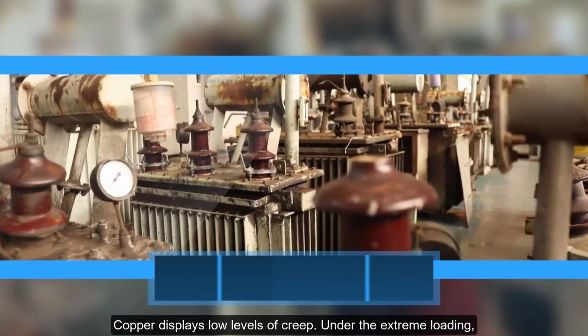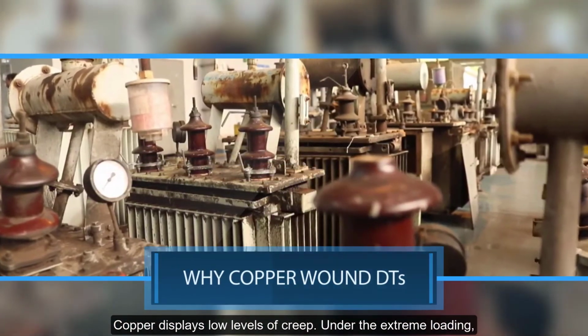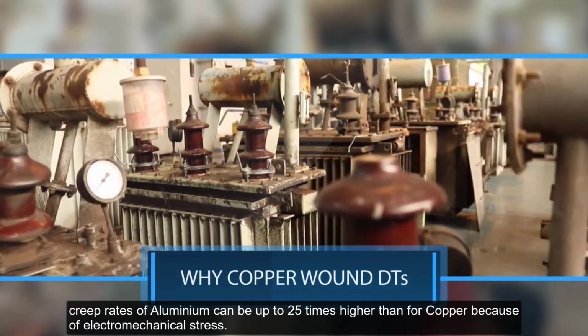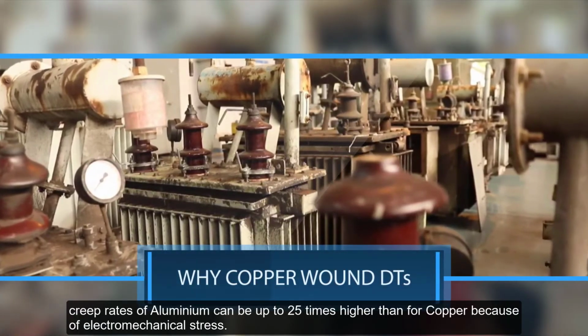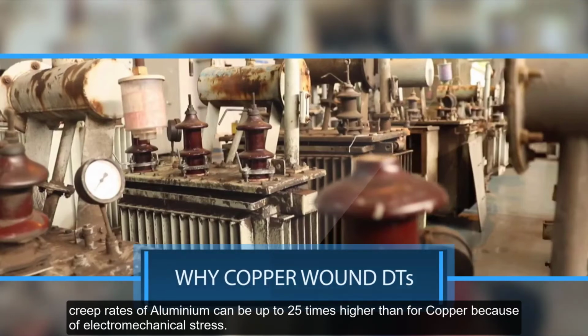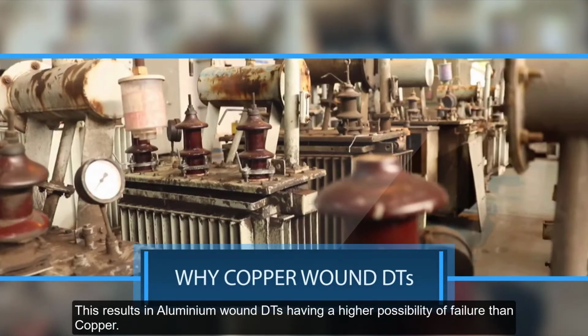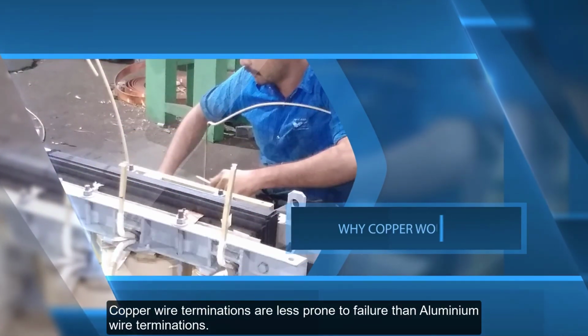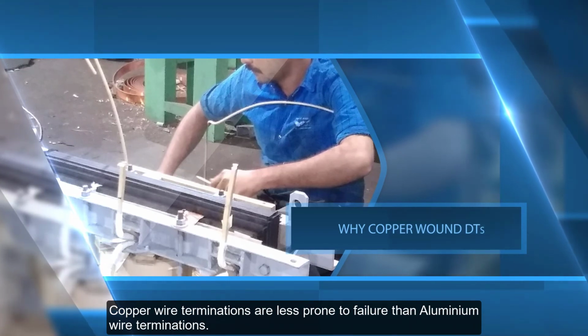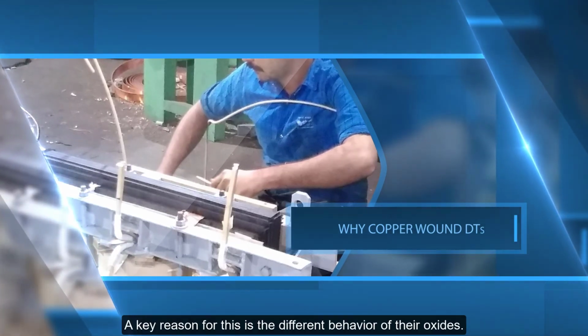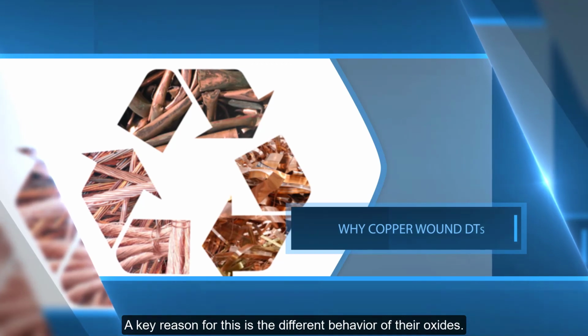Copper displays low levels of creep. Under extreme loading, creep rates of aluminium can be up to 25 times higher than for copper because of electromechanical stress due to short circuit clearance and temperature conditions of distribution transformer windings. This results in aluminium wound distribution transformers having a higher possibility of failure than copper wound ones. Copper wire terminations are less prone to failure than aluminium wire terminations. A key reason for this is the different behavior of their oxides.